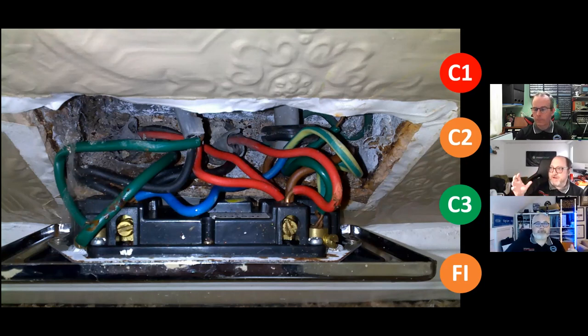To me, there's just FI because I need more information. I need to know what impact with the resistance those cables are having, with the loading, that will push me possibly into C2 territory from that. Yeah, if there's no evidence of loading or issues like that, it might be down to C3. Manufacturer might not like that many cables as well. I'd have to look into that. So there's a bit of FI work to do.